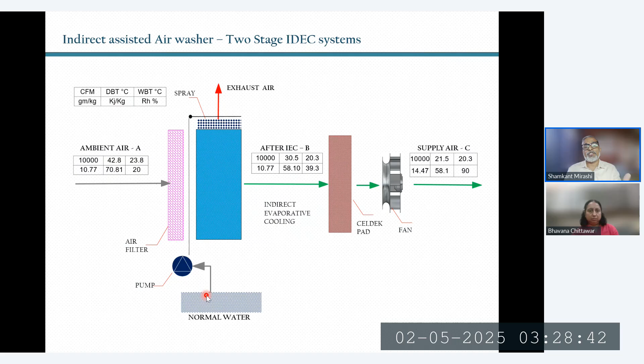Now, if one puts this number in perspective, from 70 kilojoules to 58 kilojoules, this enthalpy removal will translate into X amount of tonnage. And if you see how we have achieved that tonnage, and the electrical load to do this, the translation looks something like 200 watts per ton or 300 watts per ton, as against air conditioning, where we all know we talk about 1000 watts per ton or 1200 watts per ton. Well, with this technology, we can remove the enthalpy and cool the air with a low power penalty, as low as 200 to 300 watts, right? So here we are talking about technology which can pre-cool the air at very low power penalty.